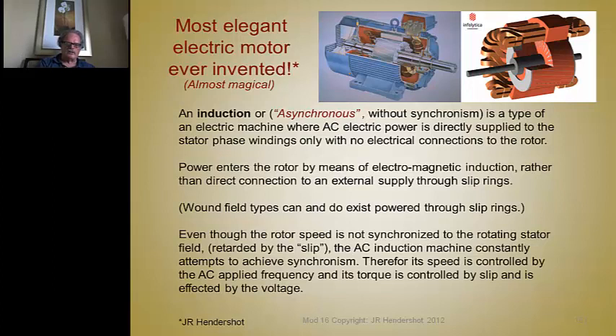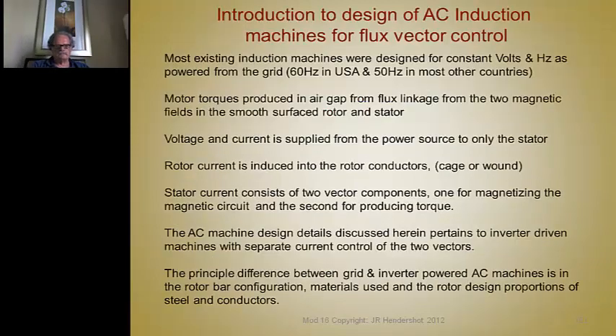Now, the greater the slip, the higher the torque, but that's not a good way to control torque. You can also control the torque by adjusting the voltage, but that's not a good way to control it either. We could study the pros and cons of why I say those methods aren't good. We can see that from the classic torque speed curve of an induction machine when it's driven by constant voltage and frequency, which we'll look at.